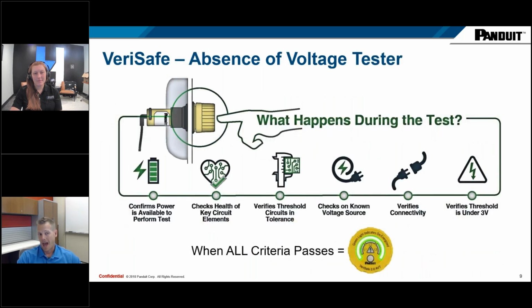Getting into exactly what happens when you push the button, because it's an electrical device. You push the button and you're trusting your life with it, right? It's a big thing. It's not like you're just flipping a light switch on and the light comes on. There are quite a few steps that it does that give this the confidence, right? So when you push that button, it doesn't just check for voltage and say it's safe or not. It goes through and confirms that there's enough power to perform the test, right? So battery indicators, it checks that the battery has enough life to complete the test all the way through. If it does not, it'll stop testing and fail.